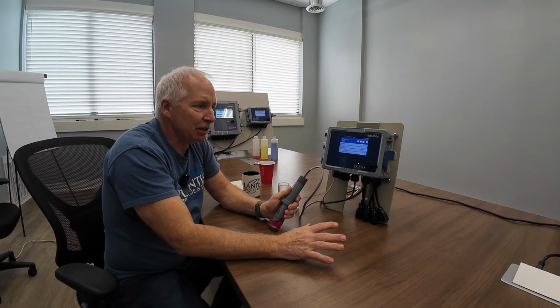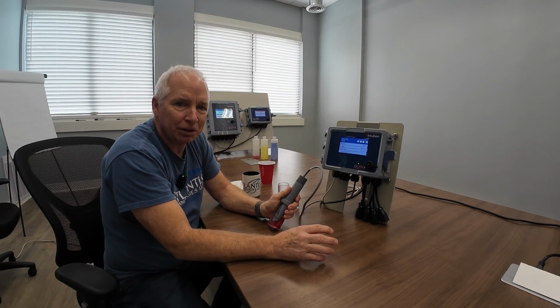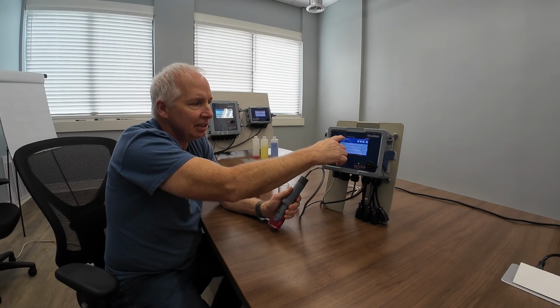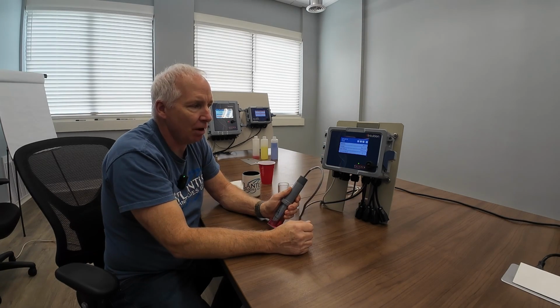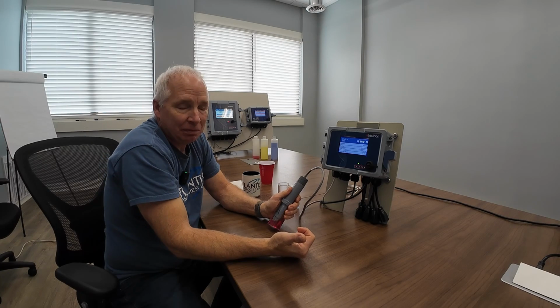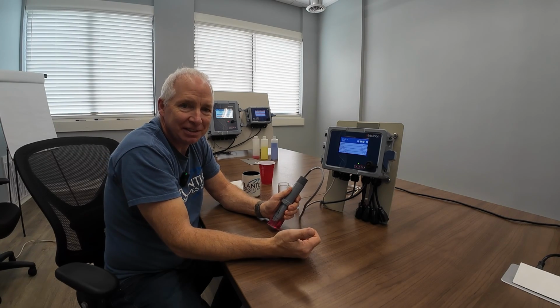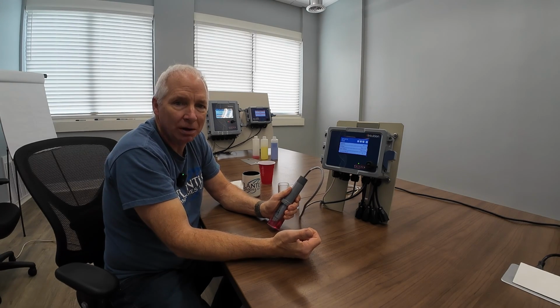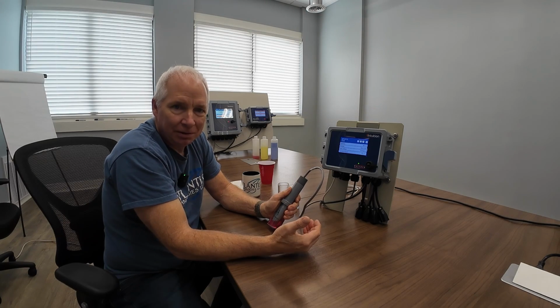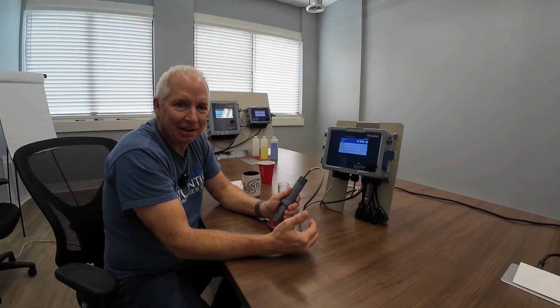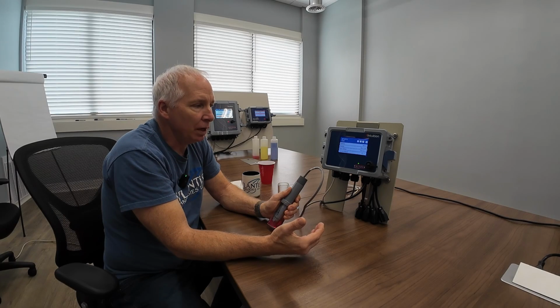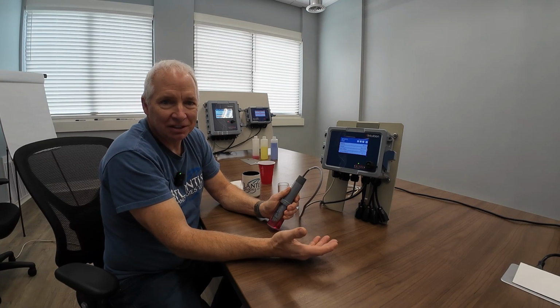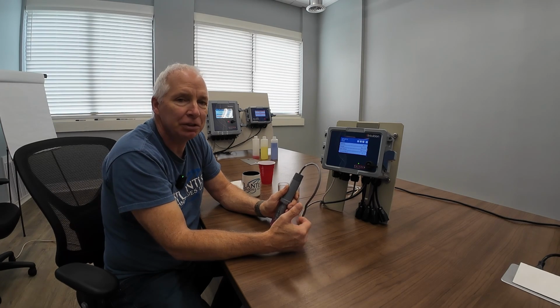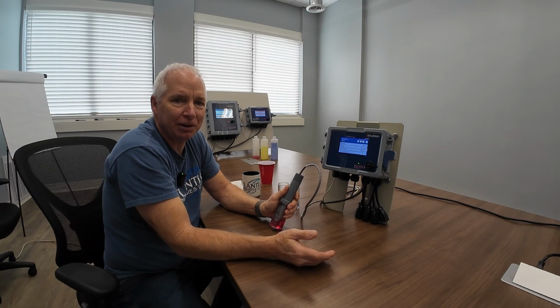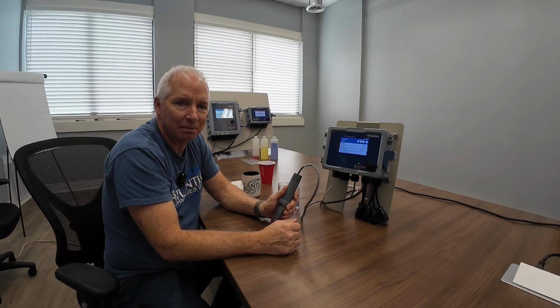But if you're concerned about your probe not functioning before you do calibration, one easy thing to do is look at the raw value. You should be theoretically around 177 millivolts in 4. You should be around 0 in 7, and you should be at negative 177 when you're in 10. So it just gives you a good indication of whether the probe's functioning or not before you even do a calibration, or if you have a failed calibration, you can go back and look at that.